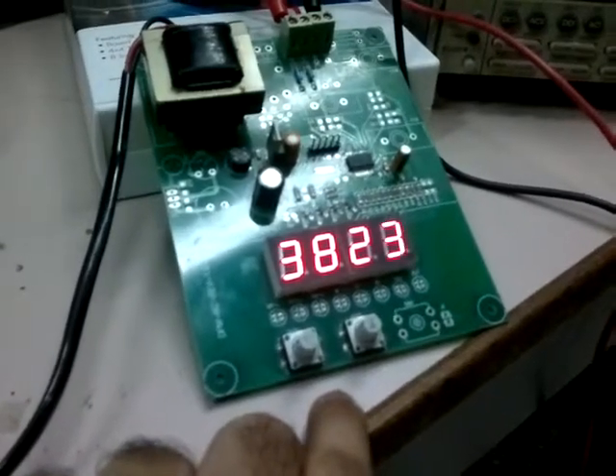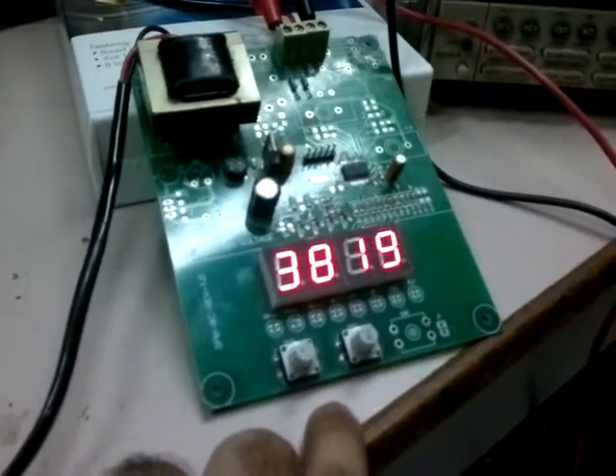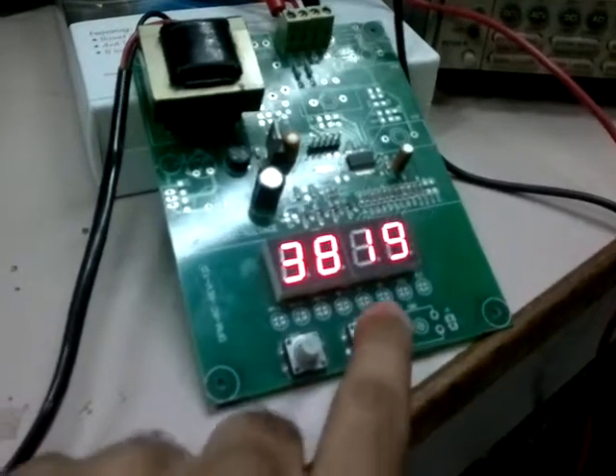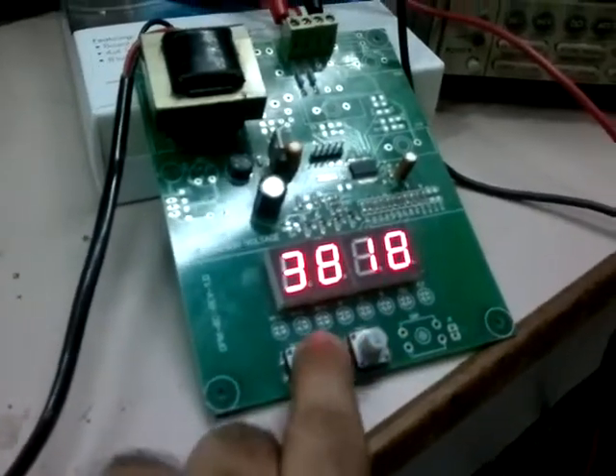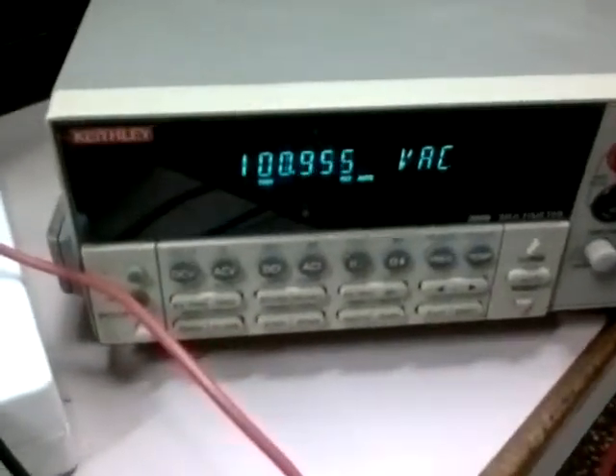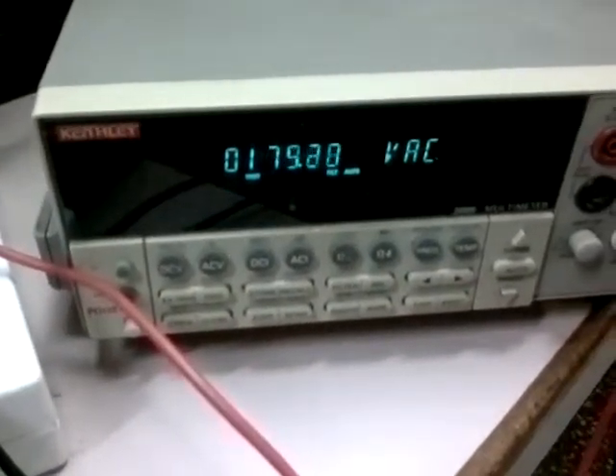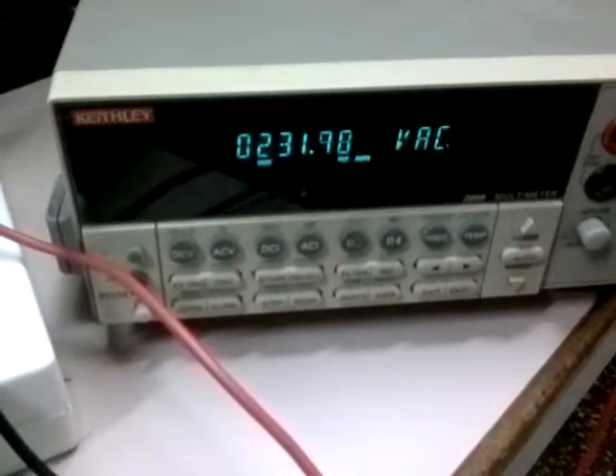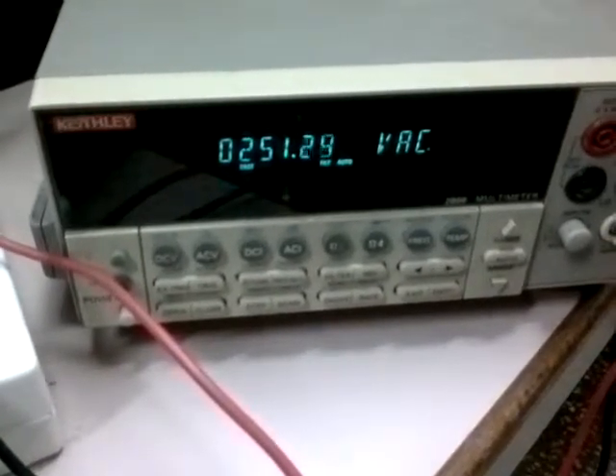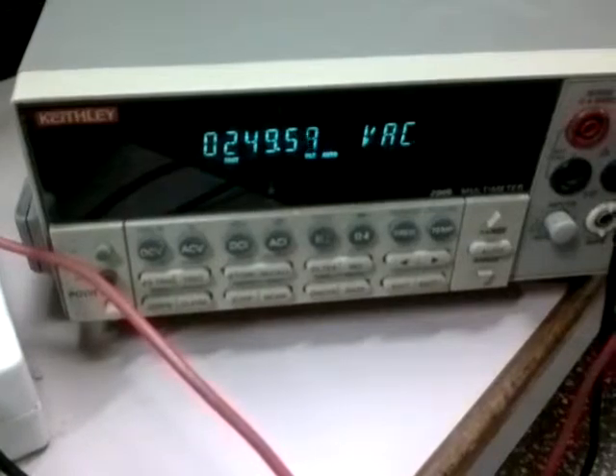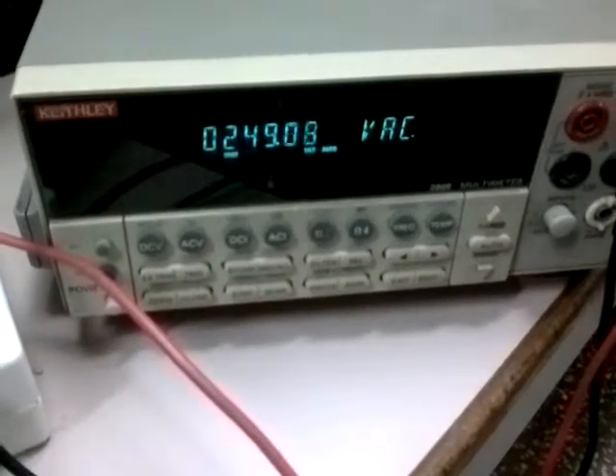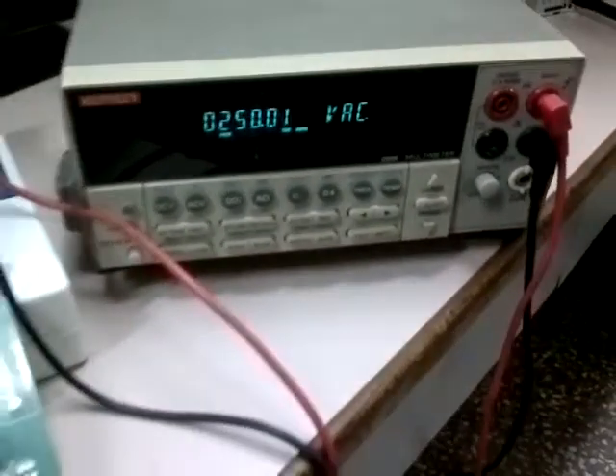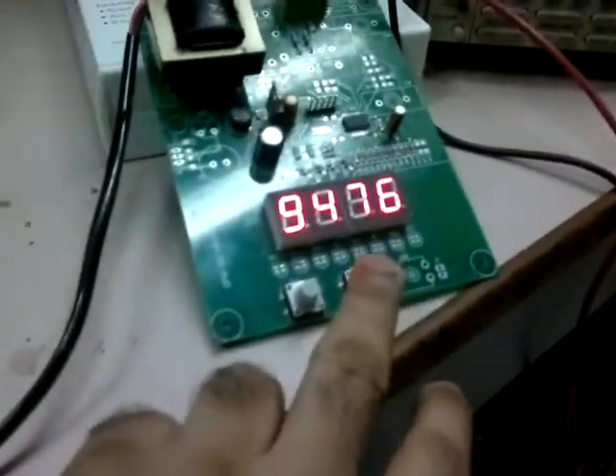This also must be 100 volts, but here the gain changes, consequently you can see the change in the raw counts. Now this is the third point for calibration. This must be 250 volts. So now this we have to enter.